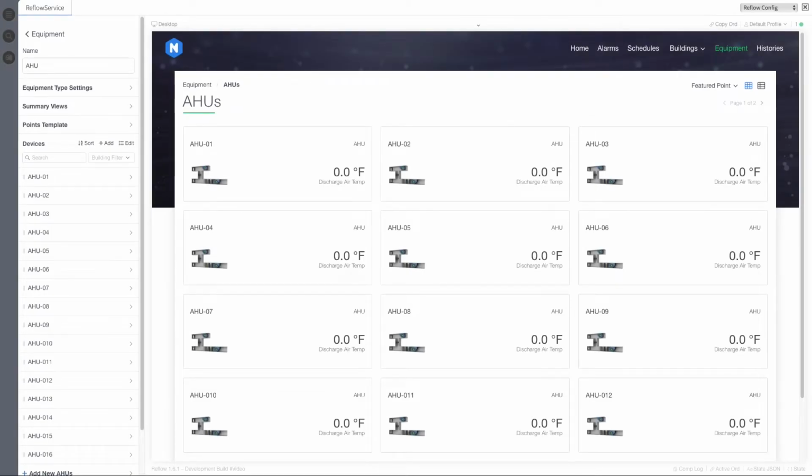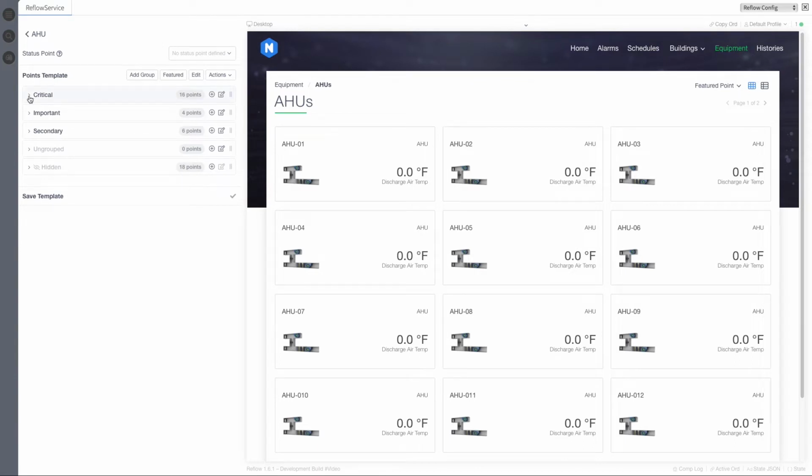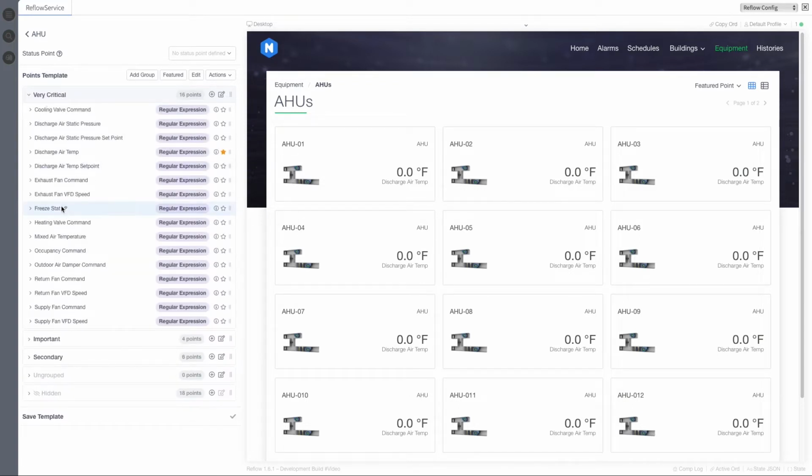We talked about the structural change, so let's see what that does in action. The biggest takeaway we expect you'll notice is the reduction in the number of times you need to run a point remap. Unless customized and overridden on a specific device, any group, group name, point order, and point display name will automatically update to any device that adheres to the point template.